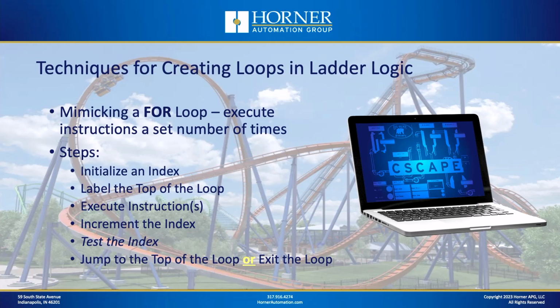We need to increment our index. So the index that counts how many times we've gone through the loop, we need to manually increment that in ladder because it doesn't automatically happen on its own like it would with a for loop. We need to test the index. Have we reached the maximum number of times we want to go through our loop? Yes or no? And then if we still need to go through the loop more times, we need to jump to the top of the loop. Or if we've already gone through the fixed number of times, we need to exit the loop. So those are effectively the steps we're going to take to mimic a for loop.